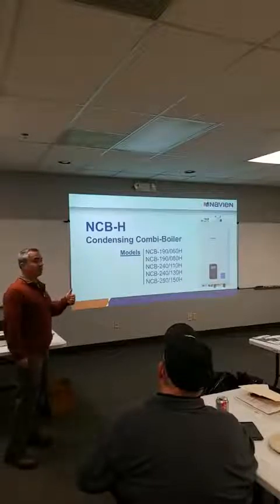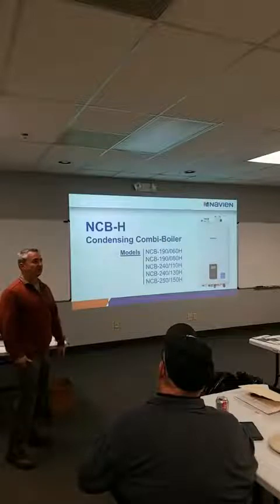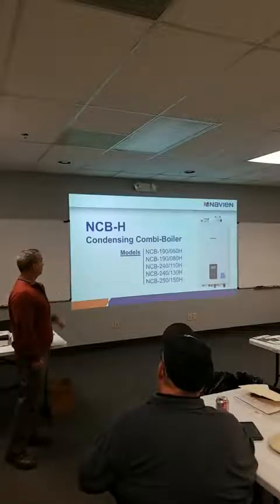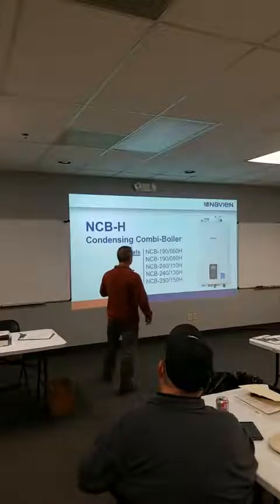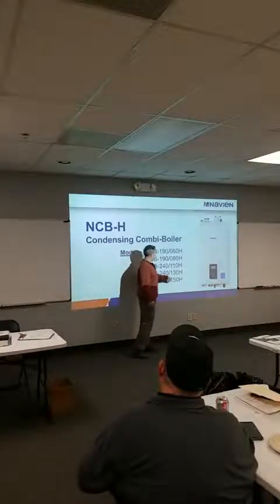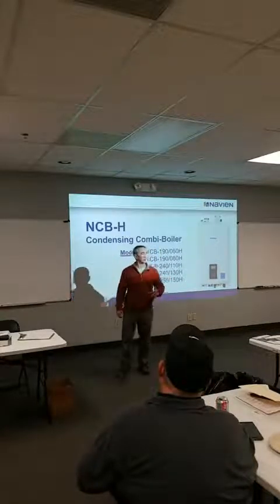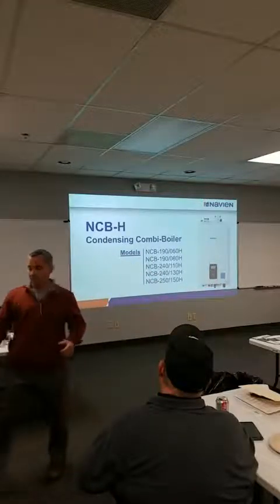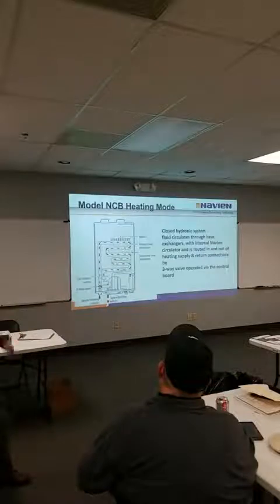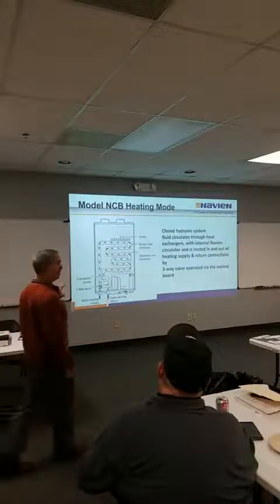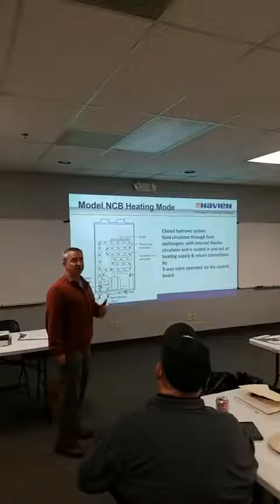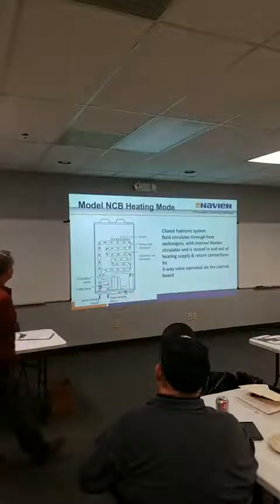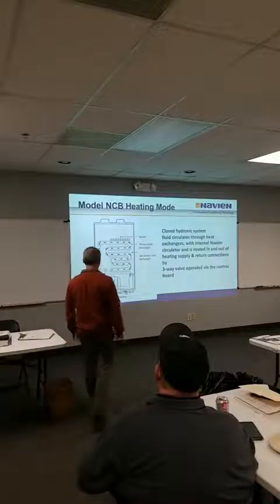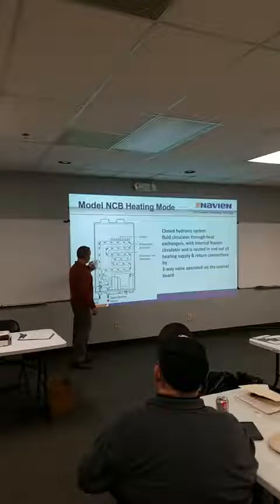So our NCB combi, we basically took all the advancements we came out last year with our fire tube combi and put them in our NCB combi. So we're selling 5 different BTU sizes of this unit, and the second number tells you your input BTUs on the heating side. You're gonna get full BTUs on the domestic hot water side, but you're gonna get limited BTUs on the heating side, because we're using our water tube heat exchanger here, and we're giving you a primary pump. We can only get so much water through that system and so much heat out of that on the heating side. So when this thing is in heating mode, basically, it's always a boiler, and then we put this little flat plate heat exchanger in there to provide your boiler heat from your domestic heat.